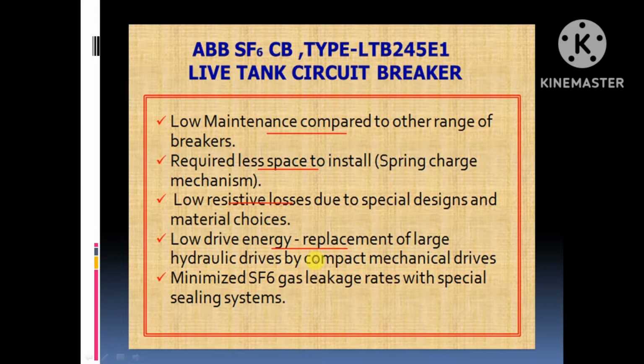Because in early days, and even nowadays in some substations, you will find a pneumatic type mechanism that occupies more space. An additional compressor is required, and the maintenance is also more, whereas spring operated SF6 circuit breakers require very little maintenance and very little space. And it is also a live tank type circuit breaker. Its SF6 gas leakage rates are very low because the quantity of gas is very small in live tank circuit breakers, whereas a dead tank occupies more space and requires more gas.